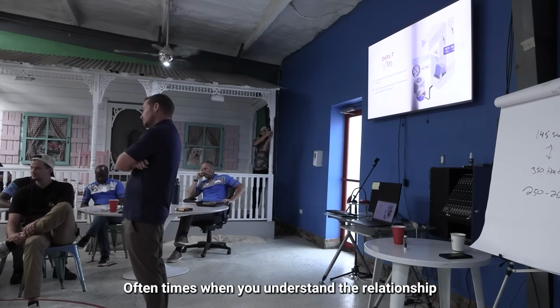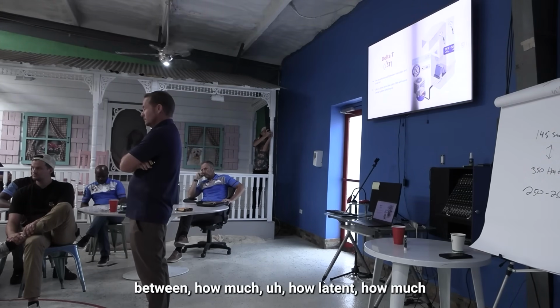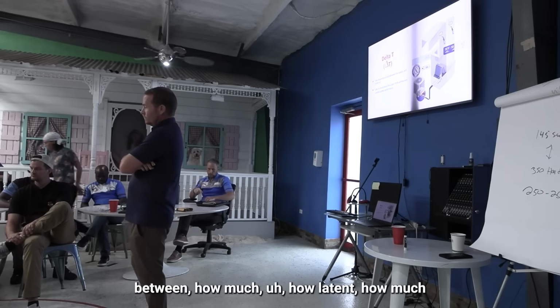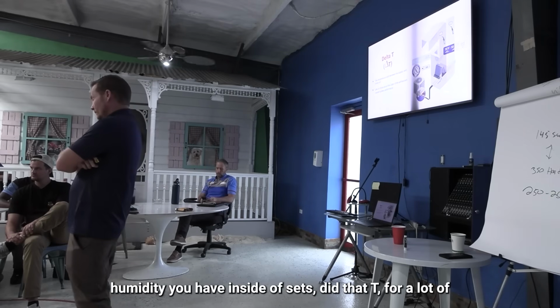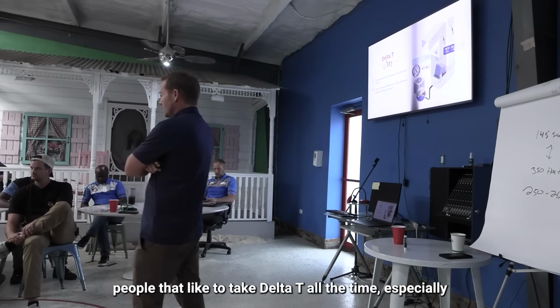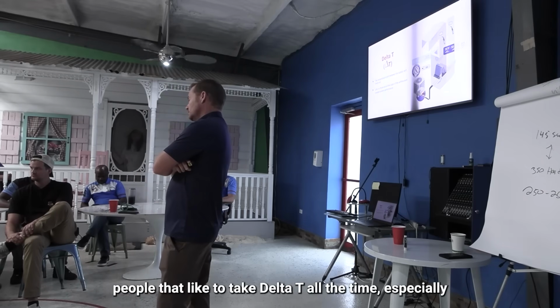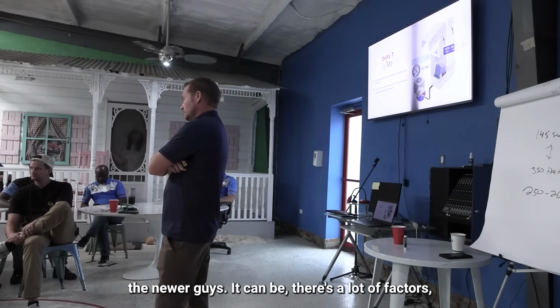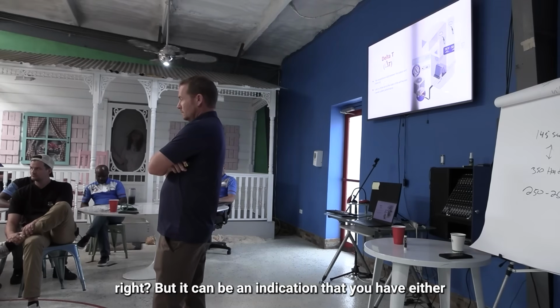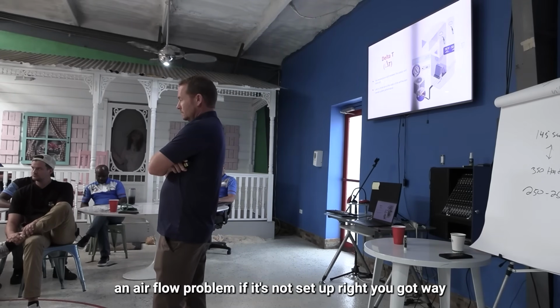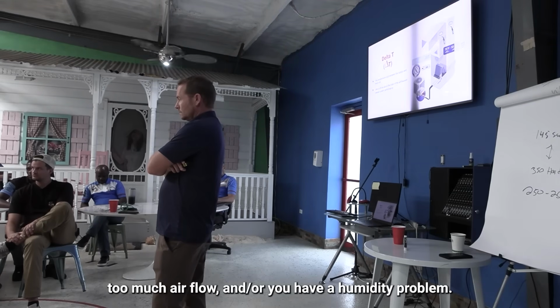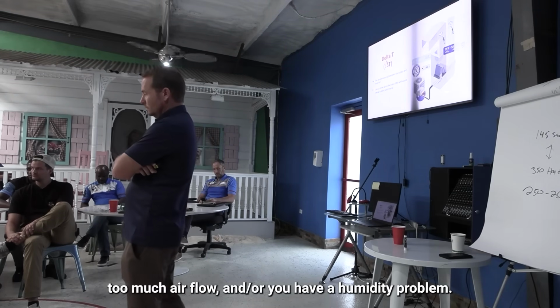Oftentimes when you understand the relationship between how much humidity you have inside, it affects the delta T. For a lot of people that like to take delta T all the time, especially the newer guys, there's a lot of factors. But it can be an indication that you have either an airflow problem, if it's not set up right, you got way too much airflow, and or you have a humidity problem.